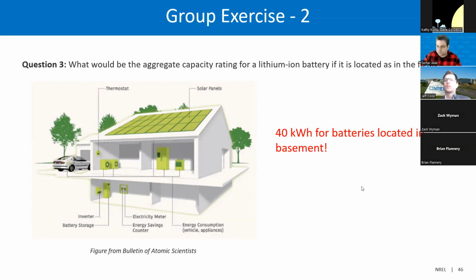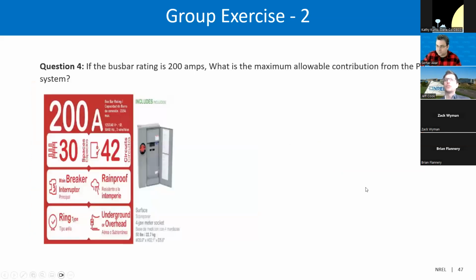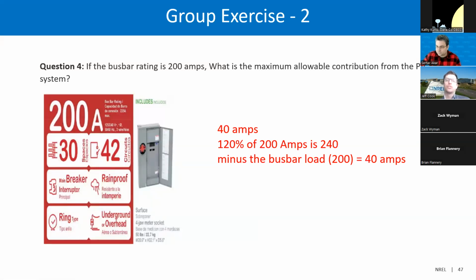All right, and I think we can move to the final one. At this point, I think we can close the poll too, so folks can see it. All right, and same question here. If you've got a 200 amp bus bar, what can your maximum contribution from the PV system be? And that's at 120% of your bus bar rating, which means 40 amps. All right, so at this point, I can pass back to you.